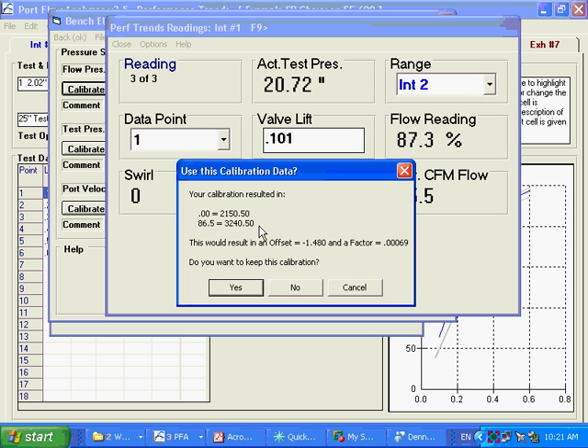4,096 counts is 0 to 5 volts. So anyway, this counts was at 0 volts or 0 pressure. 86% was at this many counts, and it resulted in this offsetting factor. Now, if you saw these two count readings being almost the same, it's an indication you didn't do something right. They should be significantly different. You see, they're over 1,000 counts difference, which is good.